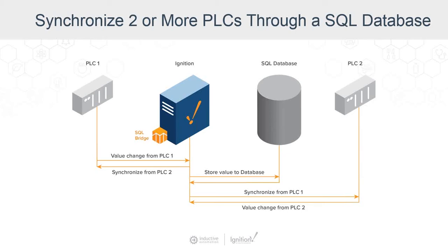We can use a database as the center of our model. Using a transaction group in the SQL Bridge module, we look at both PLCs. When a value changes in PLC 1, it gets synchronized to the database, which then synchronizes it to PLC 2. If the value changes in PLC 2, it synchronizes to the database, and that change propagates down to PLC 1. We can effectively use two transaction groups to synchronize two PLC values bi-directionally, using the database as the middle of the model.